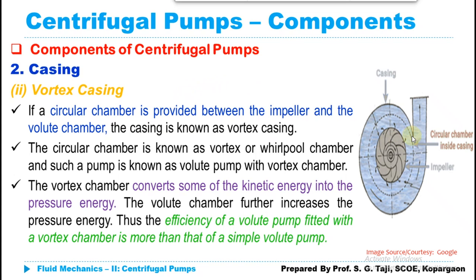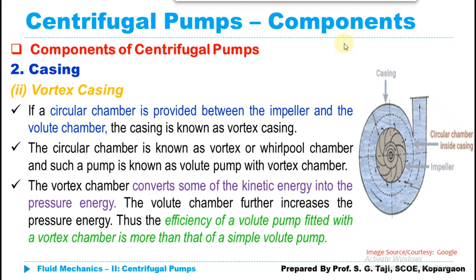The second type is the vortex casing, where a circular chamber is provided between the volute casing and the impeller. This vortex casing provides additional conversion of kinetic energy into pressure energy. Liquid coming out from the impeller first passes through the circular chamber — converting some kinetic energy to pressure energy — and then moves into the outer volute ring for further conversion. This double conversion improves efficiency and provides higher head at the outlet compared to a simple volute pump.